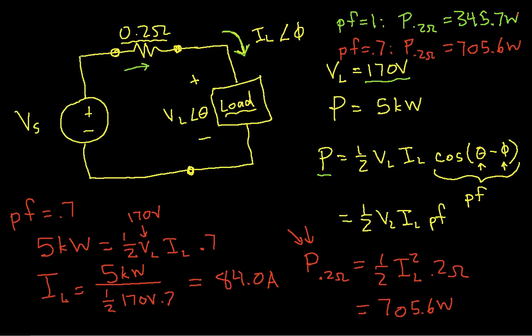So if you think about it, if you're the power company and your job is to deliver 5000 watts to the load, you have to generate more electricity with a power factor of 0.7 than you do with a power factor of 1. Because more of your power is going to be lost in transmission. So this is why utility companies really like to have power factors close to 1.